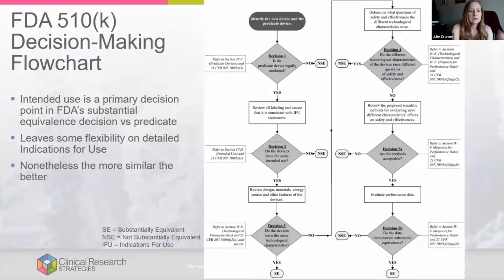Decision 1 is, the predicate device legally marketed? If it's not legally marketed, then you can't use it as a predicate device. What you want to do once you realize it is legally marketed, you want to review all the labeling and assure that it is consistent with the indications for use. That's what the IFU is here. Indication for use statements. So you're comparing those two between your device. That's why you need to define your device first, then go looking for your predicate device.